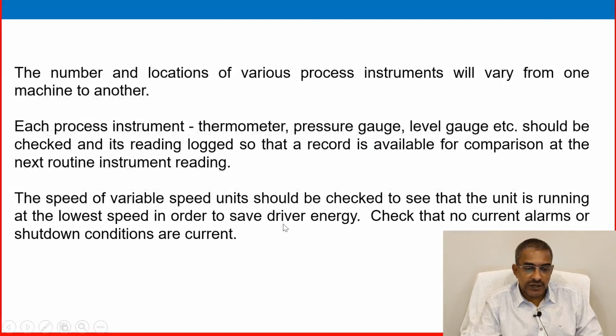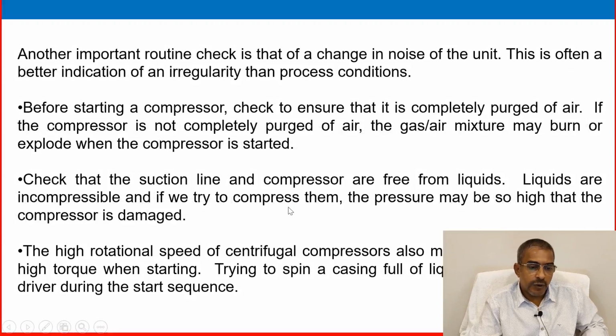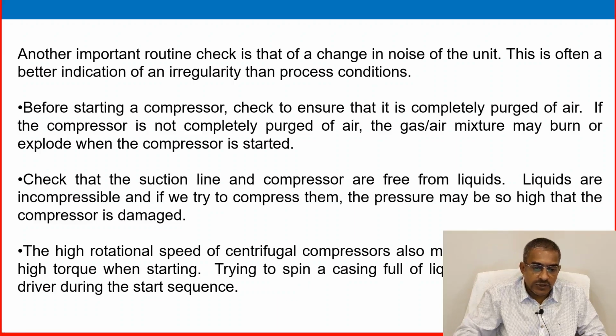The number and location of various process instruments will vary from one unit to another. Each process instrument, thermometer, pressure gauge, level gauge, etc., should be checked and its reading logged so that a record is available for comparison at the next routine instrument reading. The speed of the variable speed unit should be checked to see that the unit is running at the lowest speed in order to save driver energy. Check that no alarms or shutdown conditions are current. Another important routine check is for a change of noise on the unit. This is often a better indication of an irregularity than the process conditions.